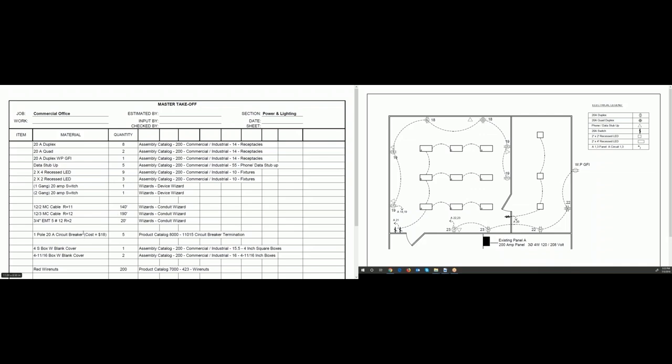Also circuit breakers — on a commercial project, they often have a panel schedule that shows the panels and circuit breakers. I just go there and count all the circuit breakers to input into Red Rhino to capture the labor. The circuit breakers cost $18. I also input a 4S box, two 4-11/16 boxes, and some wire nuts — not shown on the blueprints. There are certain things you have to see through the blueprints to know you need, and the blueprints are one-dimensional showing only a top view.